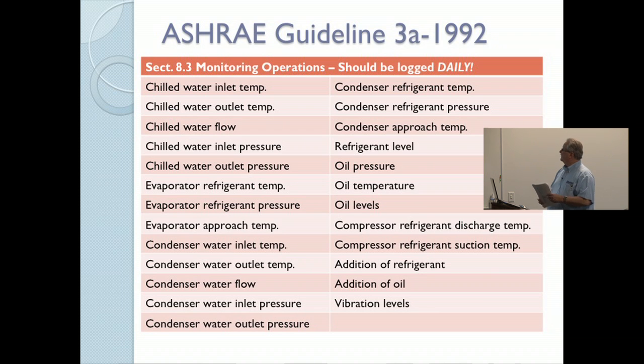ASHRAE, now this is a dated deal. I'm sure ASHRAE's come up with a later version of their Guideline 3A. But ASHRAE Guideline 3A suggests what you should do to maintain your chiller. They are saying that if you're doing your chiller maintenance right, you are doing daily logs, at least, of all this data on your chiller, if it's valid for your chiller.